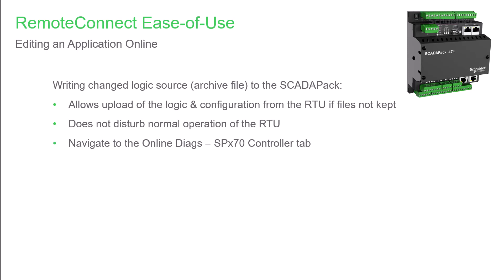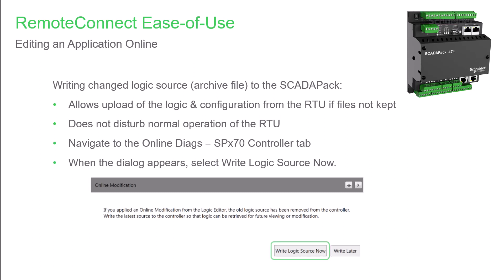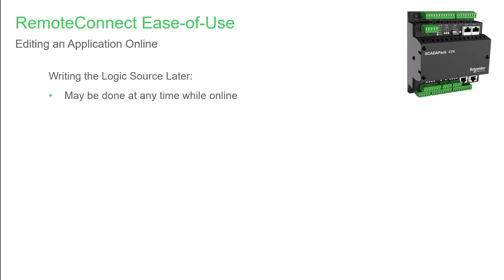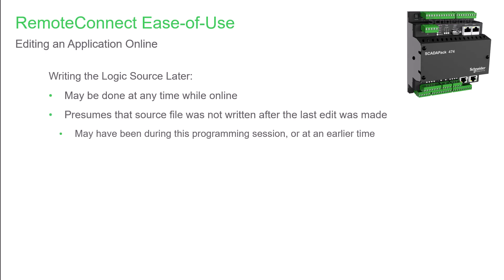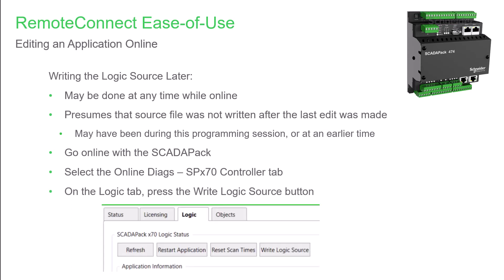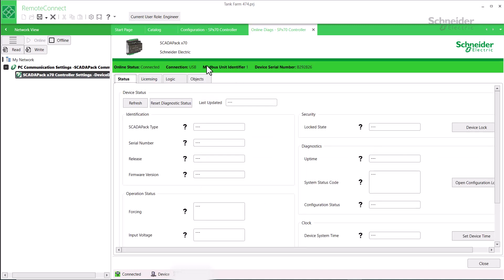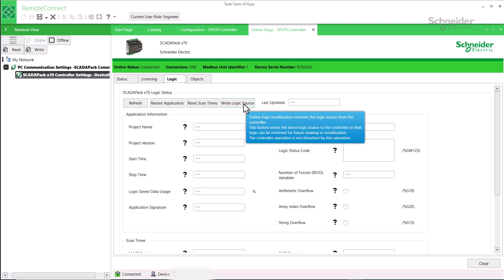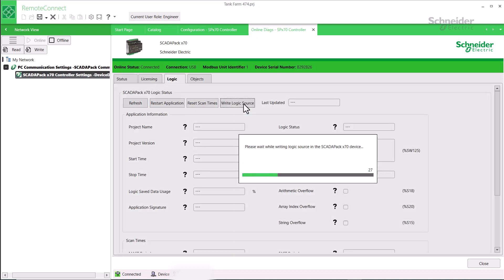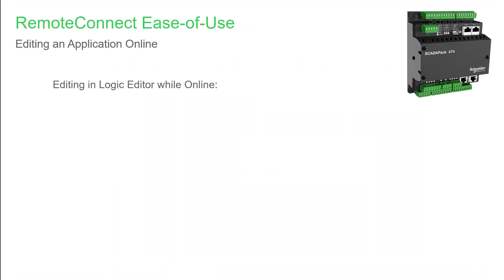If you've done online edits in this programming session, navigate to the Online Diags SPX70 Controller tab. A dialog will appear, and you can click the Write Logic Source Now button. Writing the logic source, which is an archive file to the SCADAPack, can be done at any time while online. This presumes that for some reason it was not done after previous online edits were made, which might have been hours or months ago. To do so, first go online with RemoteConnect and then select the Online Diags SPX70 Controller tab. Now select the Logic tab and press the Write Logic Source button. I had made an online edit earlier by creating the new Tank1Volume object, but I didn't write the logic source at that time, so I'll do it now. I'm online with the SCADAPack, so I'll just go to the Online Diags SPX70 Controller tab. I'll select the Logic tab below that, and then click Write Logic Source.